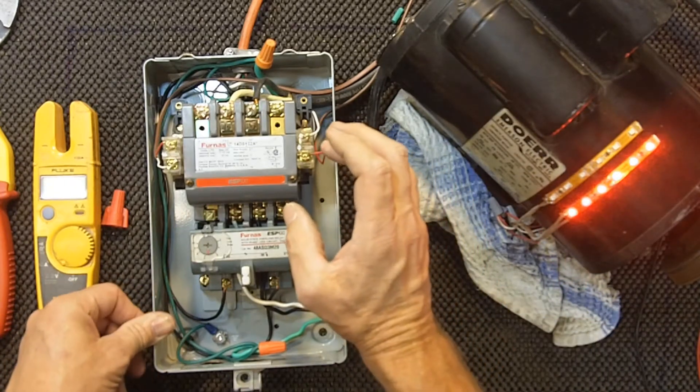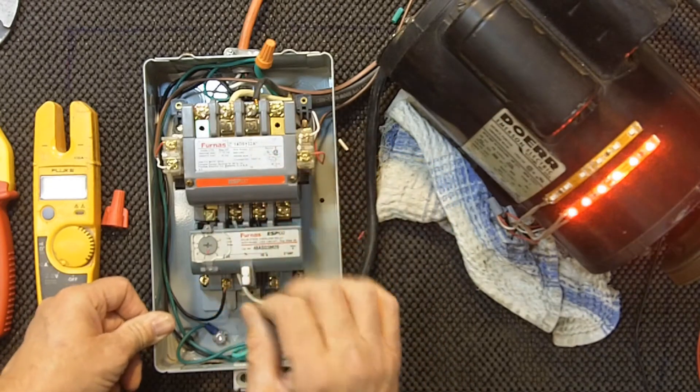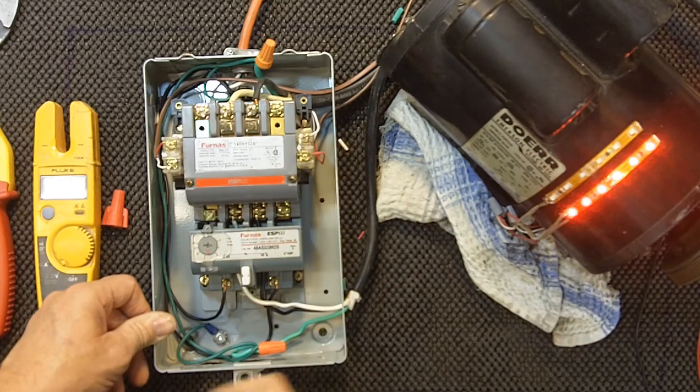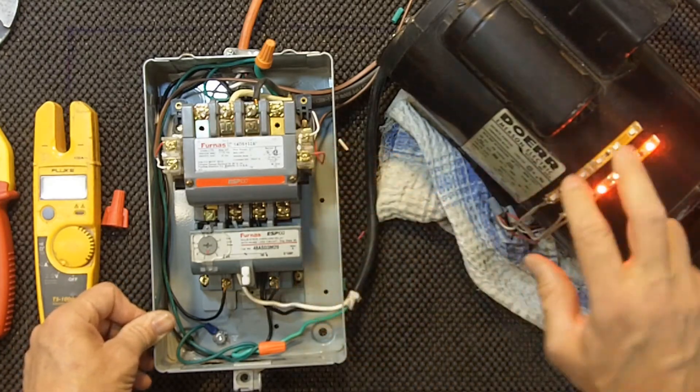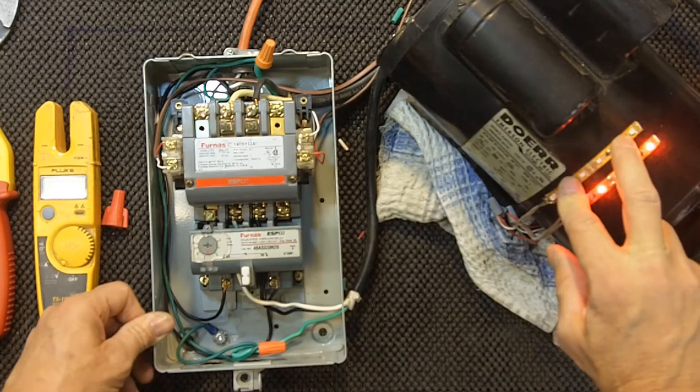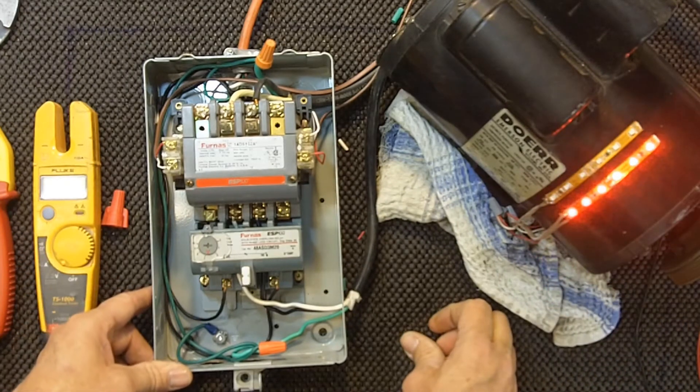On this side here, I've got the normally open, and remember the normally open, normally closed is in the de-energized state. So once this closes, then the green light will come on, and it'll let the operator or whatever know that the motor's running.